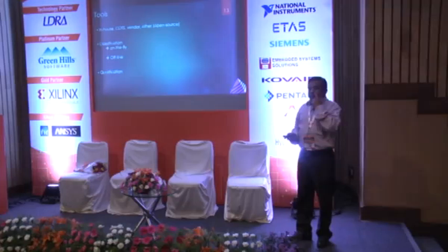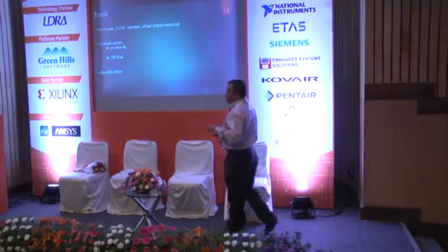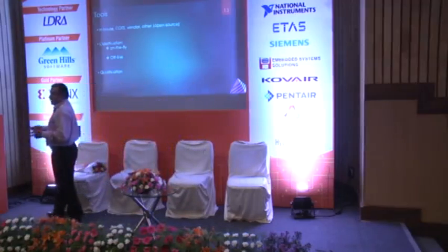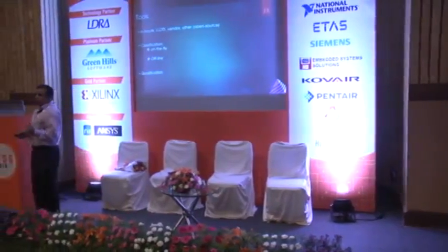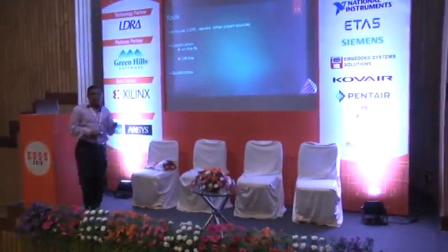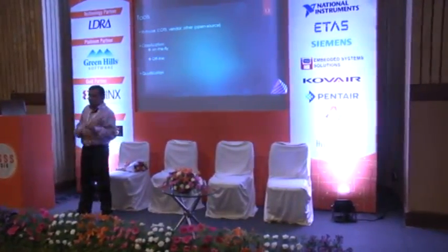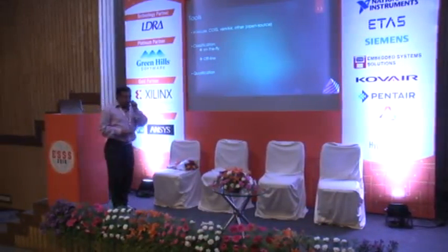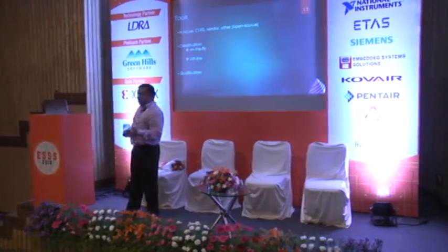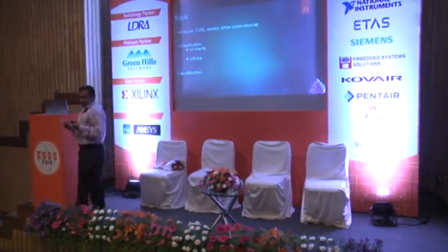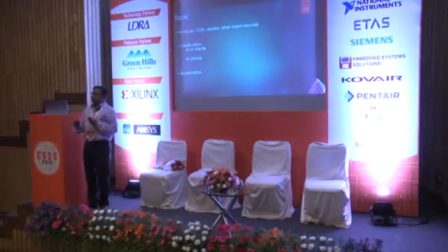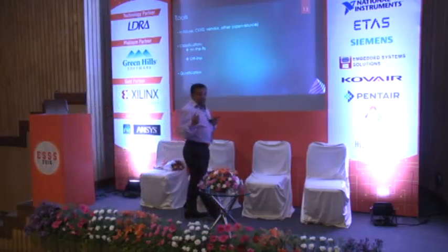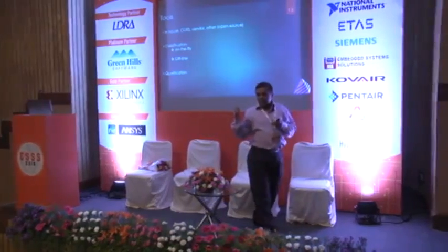So on the fly is something which will impact the performance of the software when it is running. So it is making a clear differentiation between a tool which is used and it affects the performance of the system or the software when the software is running. So typically it points to a couple of tools only where I am trying to configure on the fly. So I am setting some parameters when the software is running, so that I want a different performance or a changed behavior, and what if that is going to result in a hazardous situation.